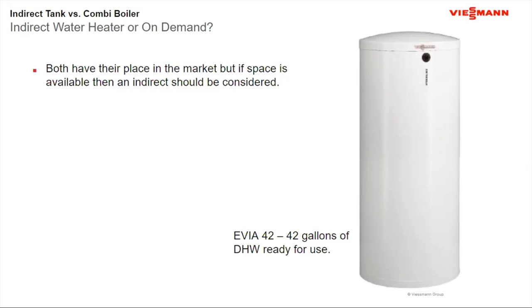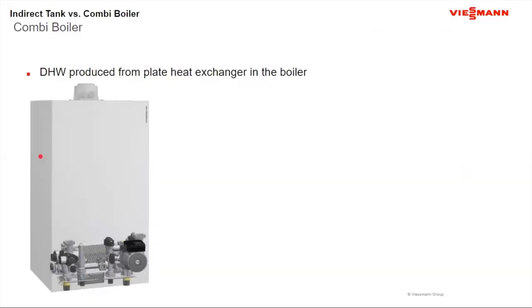So that is one of the pros in favor of the combi boiler over the indirect water heater. Okay. If I do a combi boiler, I'm producing hot water through a plate frame heat exchanger. As we said earlier, the boiler has to fire with every draw. So you end up with the boiler cycling many, many more times with a combi boiler than you do with a storage type indirect water heater.